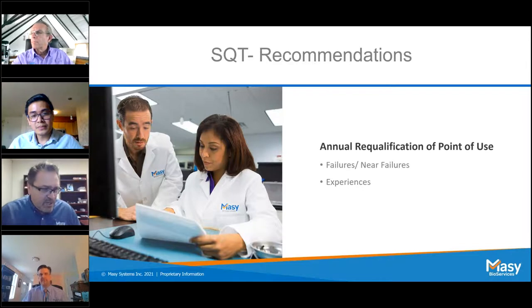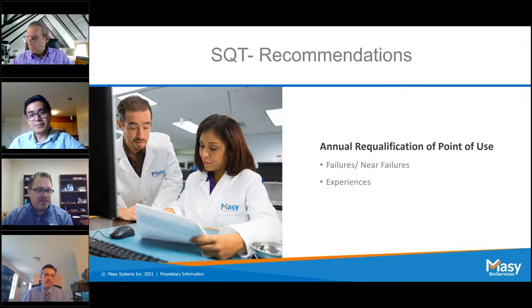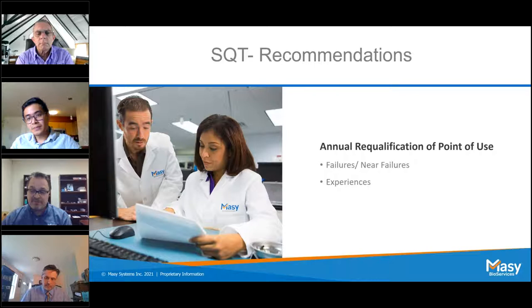Certainly. The one that seems to stick out the most for me as being troublesome is the non-condensable gas test. Something that can reveal a problem in the steam generation and delivery system, especially when a site is now trying to achieve EN285 compliance, and they're testing a system that was designed a long time ago, is older, and now you're actually performing a test on that system for the first time. So I've seen non-condensable gases be challenging.